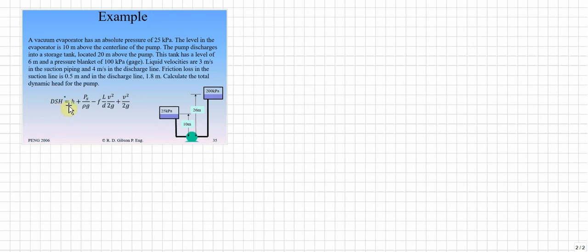All of the things that are trying to help us get the fluid into the pump minus the things that hurt us. So in this case it's going to be the height of fluid that's helping us get it into the pump. It's going to be the pressure in the tank that's helping us get it into the pump minus the friction which is going to be hurting us getting it into the pump.